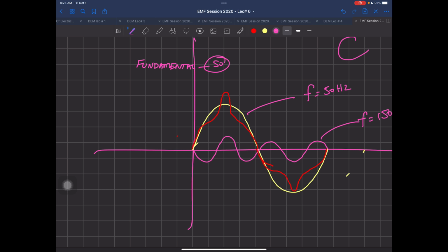But if you have a third harmonic with a frequency of 150, we know XL equals 2 pi FL. So when frequency increases, XL increases, and the current that flows is going to be deteriorated - it decreases. So the efficiency of your machine is going to be reduced.